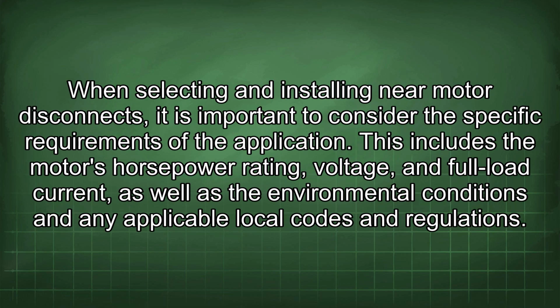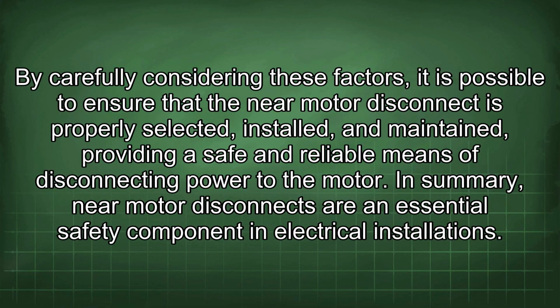When selecting and installing near-motor disconnects, it is important to consider the specific requirements of the application. This includes the motor's horsepower rating, voltage, and full load current, as well as the environmental conditions and any applicable local codes and regulations. By carefully considering these factors, it is possible to ensure that the near motor disconnect is properly selected, installed, and maintained, providing a safe and reliable means of disconnecting power to the motor.